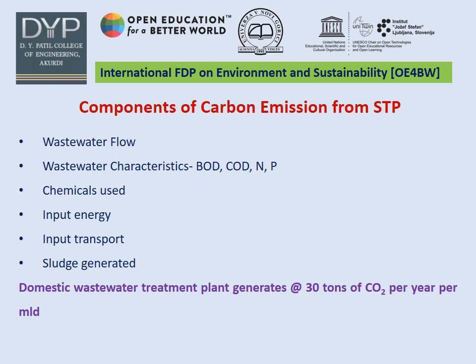The third important component of carbon emission is chemicals used in wastewater treatment. These may include external organic matter such as methanol for nitrogen removal. Coagulants such as ferric sulphate, ferric chloride, polyaluminium chloride, alum, and polymers are also used. Additionally, activated carbon, ion exchange resin, and anti-foaming agents are used, all of which form part of the carbon emission.